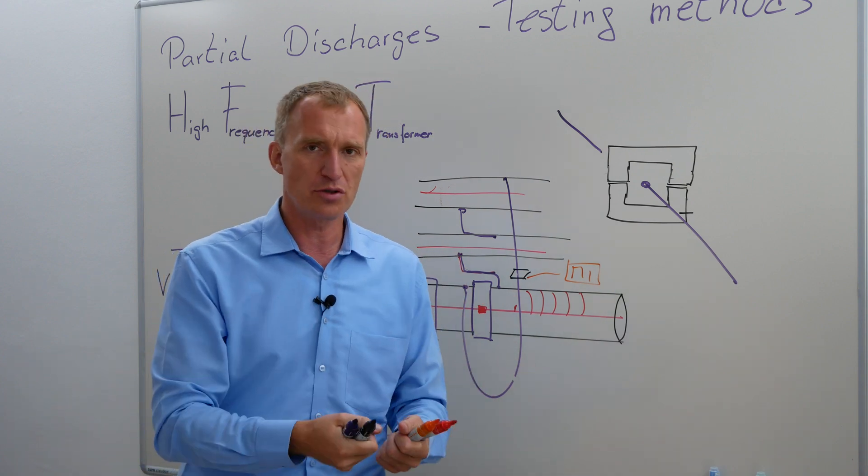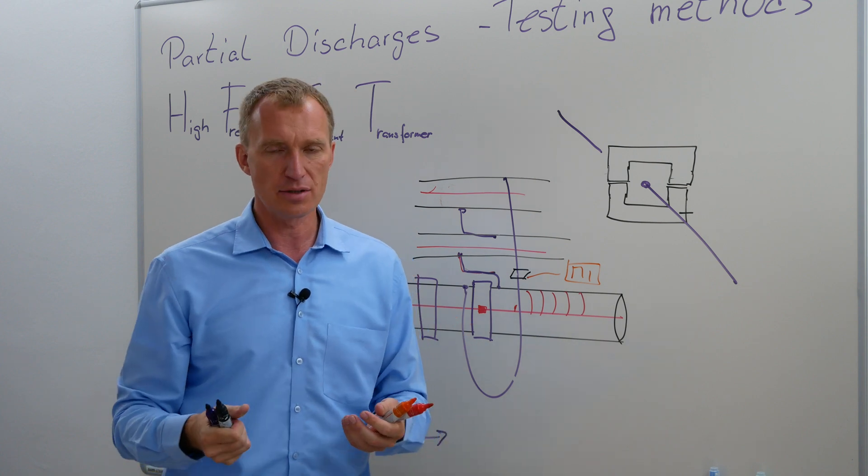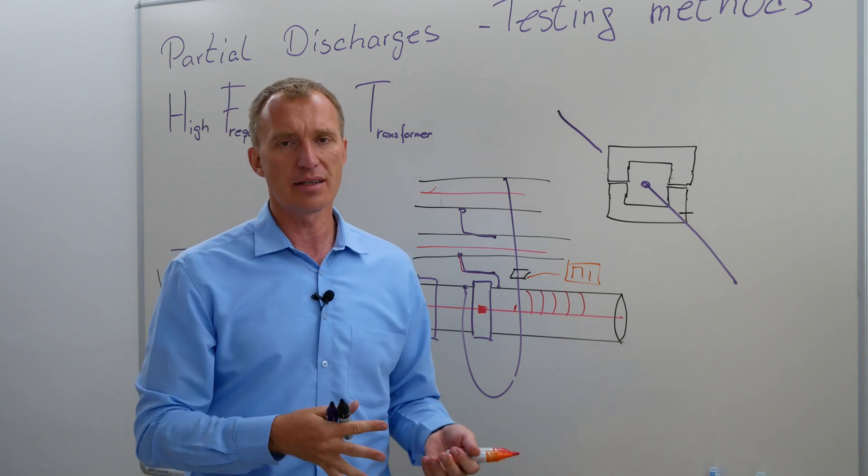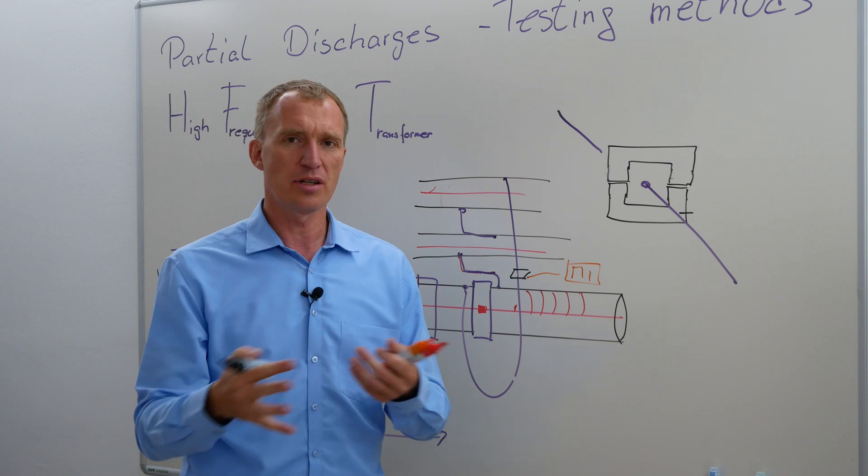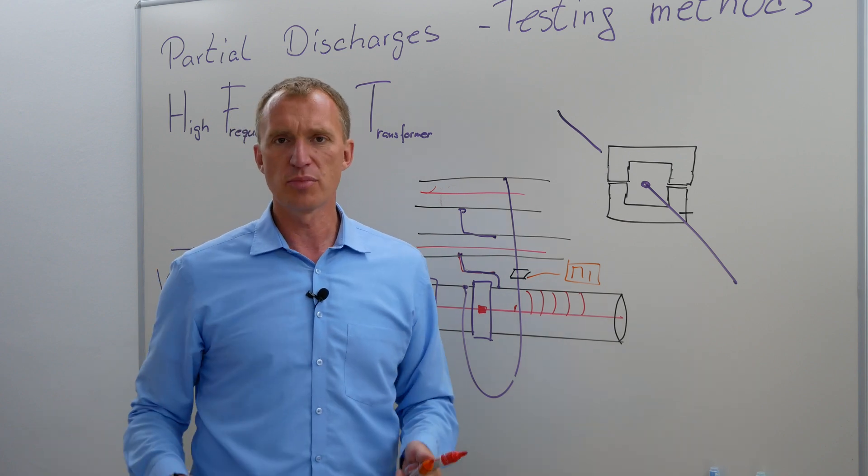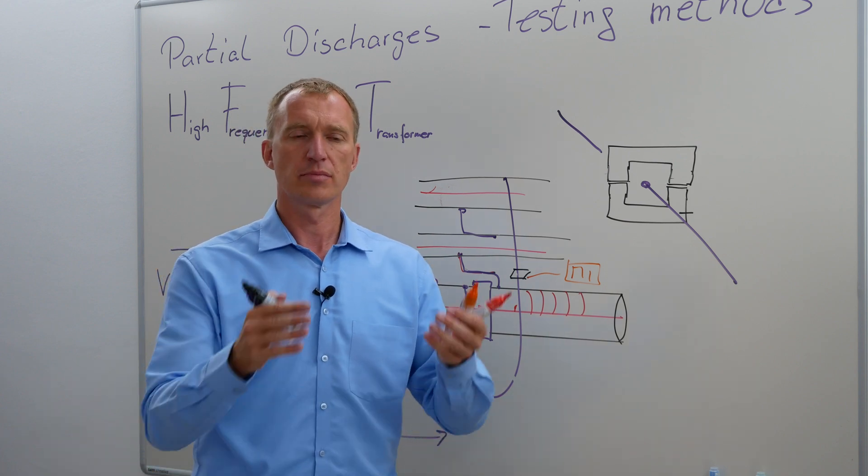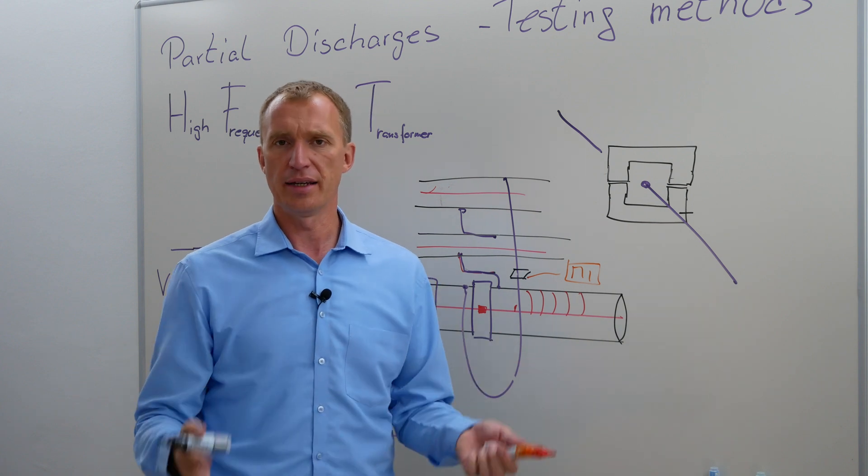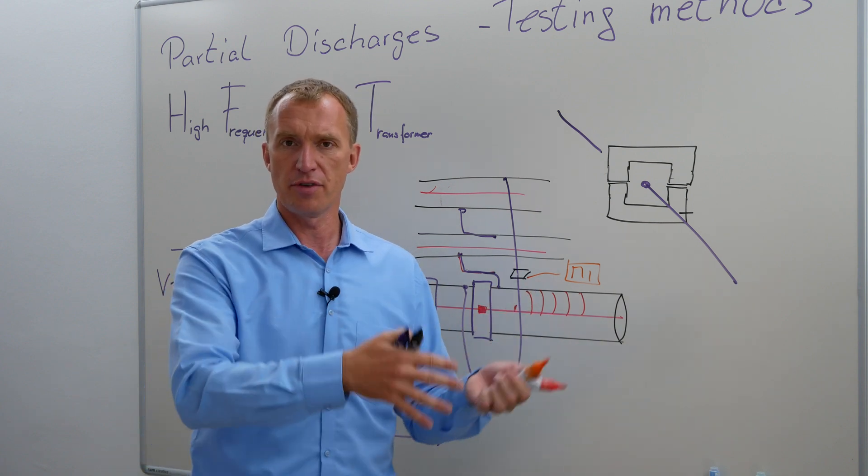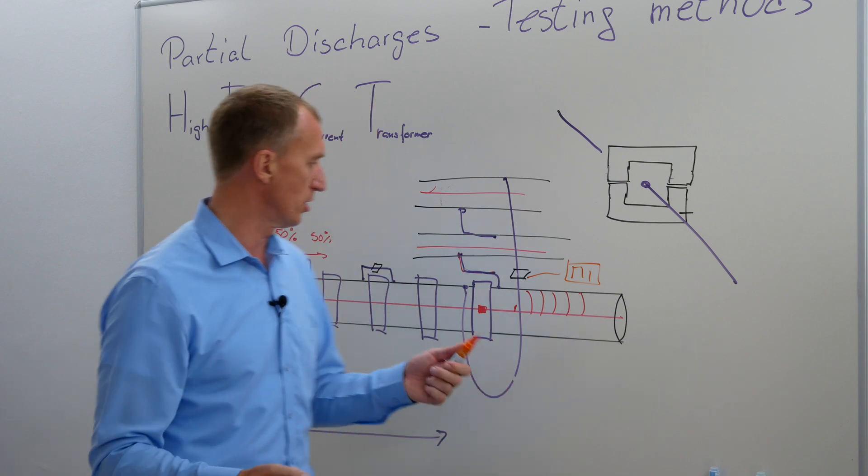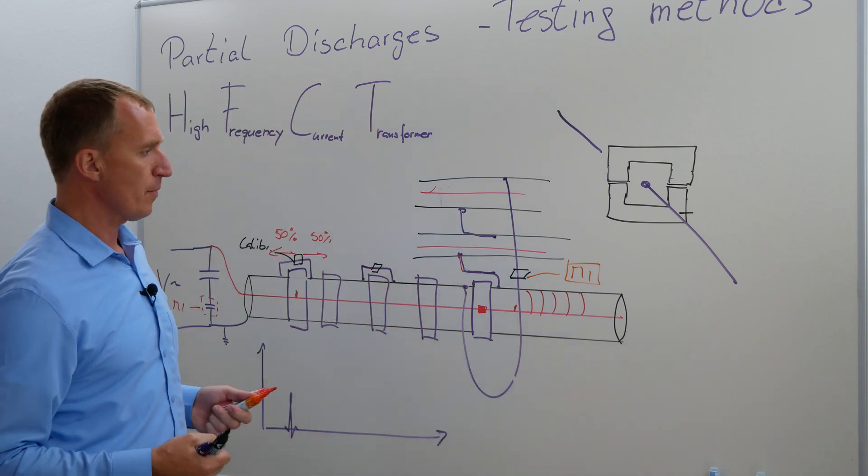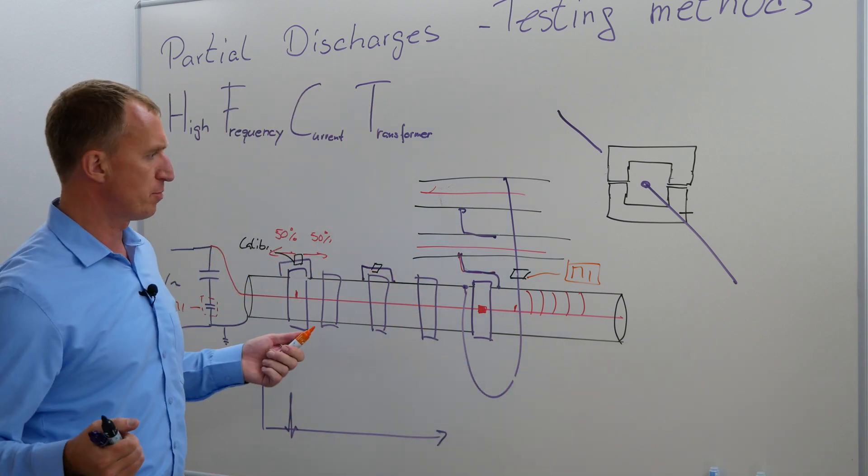Is it a real measurement according to the IEC 60270? Well, we could discuss that. Is it a real calibration? Yes or no? Let's oversimplify it and say no. It's a detection method. It helps us to figure out if there is partial discharge, where the partial discharge is. So that's pretty much it.